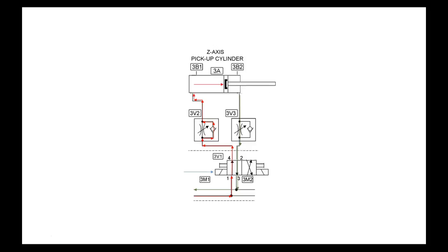On 3V2 and 3V3, what's controlling the arrow valve? These are not valves. These are sensors. These are your flow control valves right here. These are manual. You have little knobs on there you adjust for what you want the thing to run. Now, these are very, very popular. They do have what they call proportional valves, where you can literally adjust the flow. Those are analog devices. Those are not digital devices. So you might run into those. If I need to vary the speed, then you would go to a proportional flow control valve. Normally we do it manually.